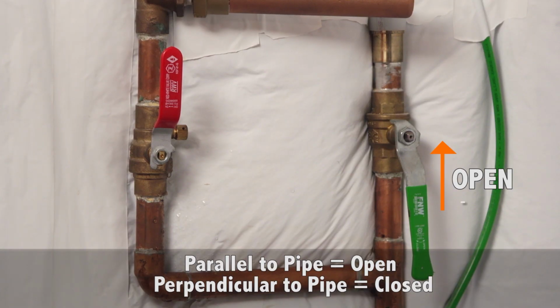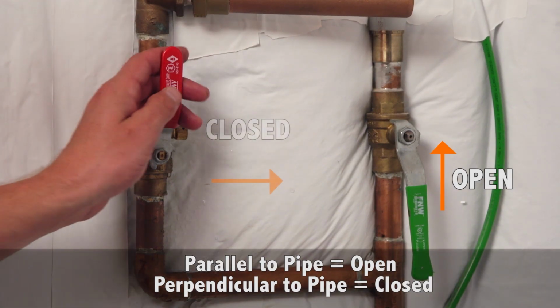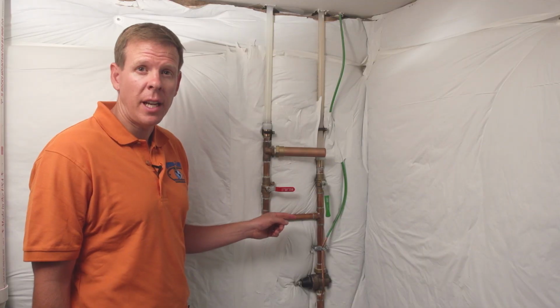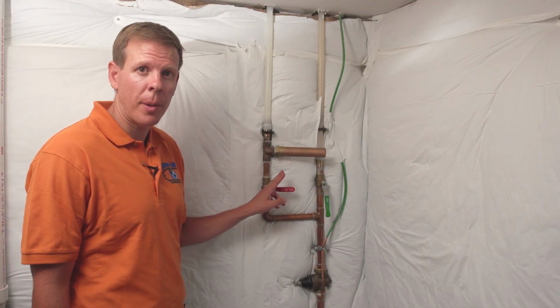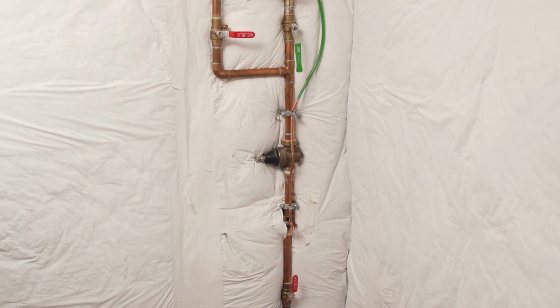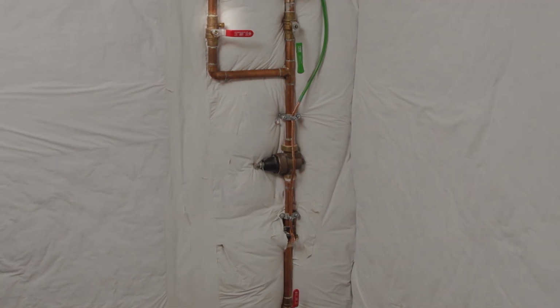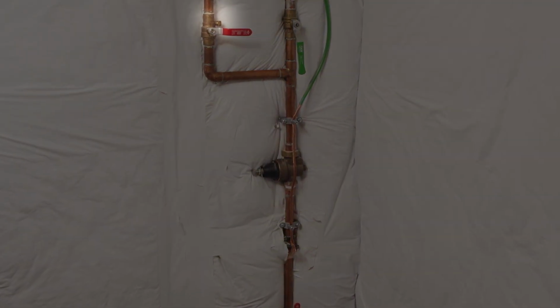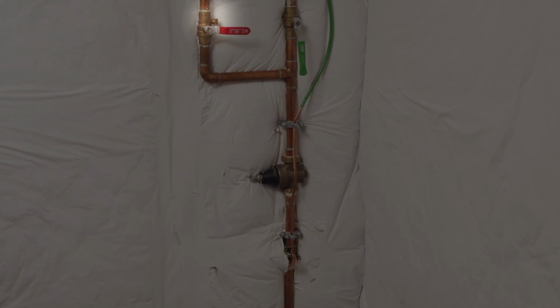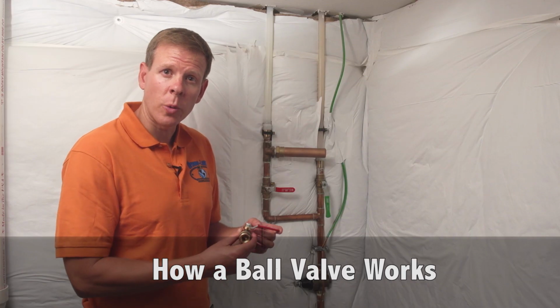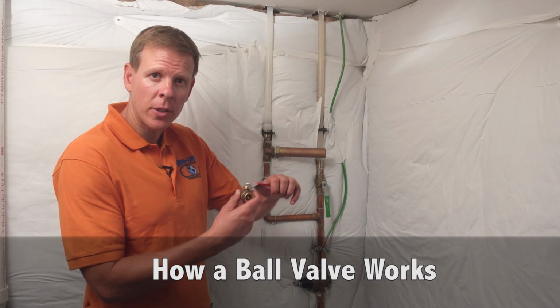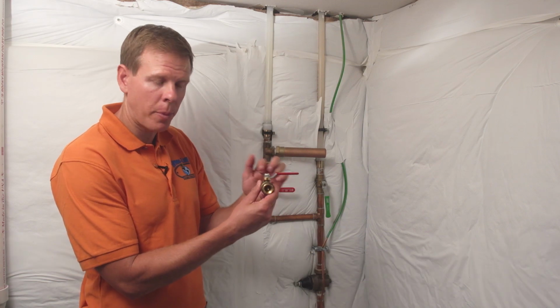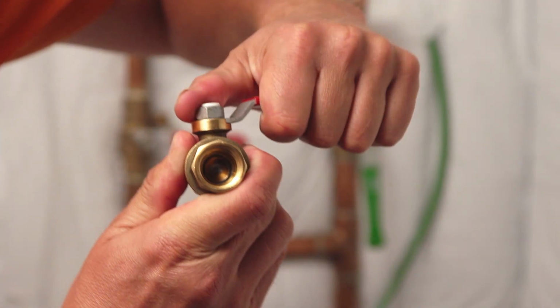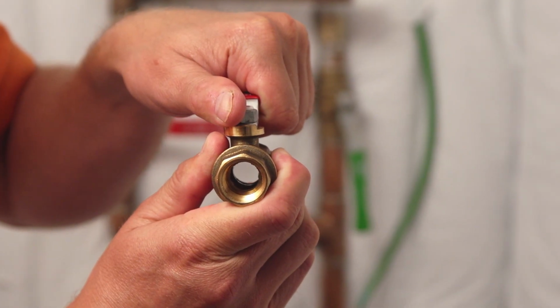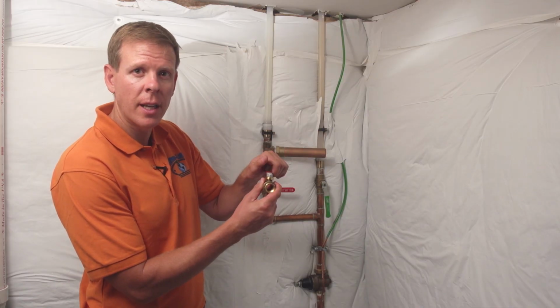To shut off a ball valve, you would turn it perpendicular to the pipe. A good hint to help figure out which valve is the proper shut-off valve for the sprinkler system is to look for a drain nipple or a drain valve in between the shut-off valve and the backflow preventer. I'm going to show you quickly the inner workings of the ball valve so you understand how it works. It is currently perpendicular, which is closed.